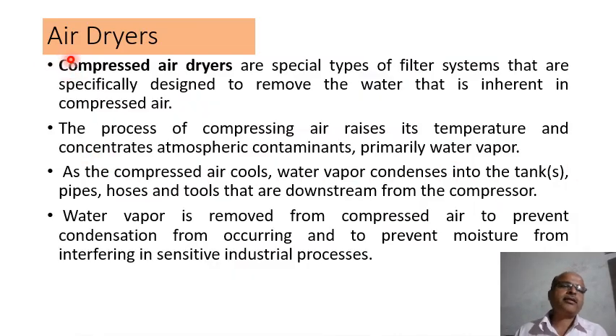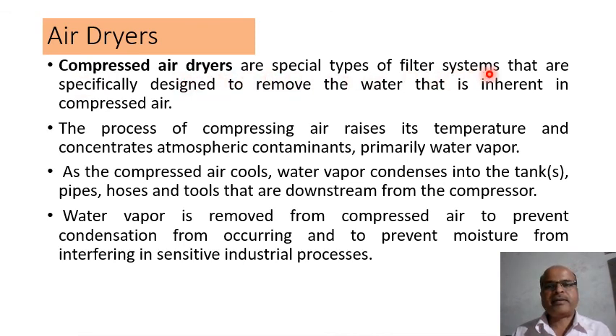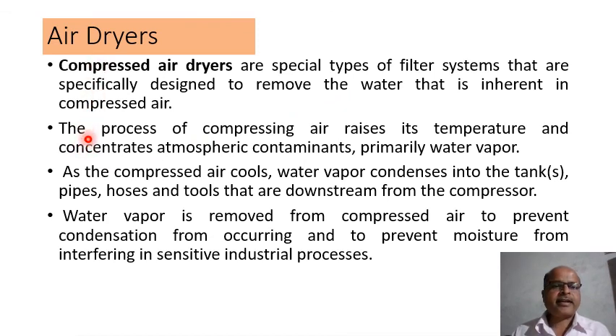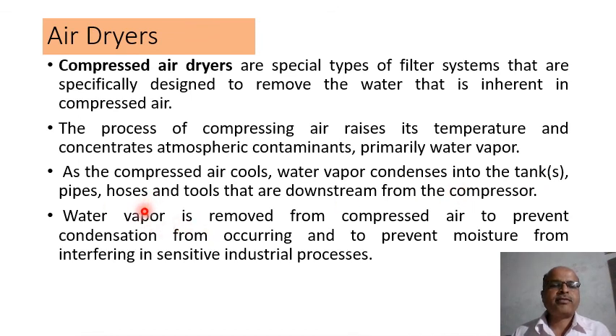The next component in a pneumatic system is air dryers. Compressed air dryers are special types of filter systems specifically designed to remove water that is inherent in compressed air. When air is compressed, water vapors are generated due to the cooling effect and must be dried. The process of compressing air raises its temperature and concentrates atmospheric contaminants, primarily water vapor. As compressed air cools, water vapor condenses into tanks, pipes, hoses, and tools downstream from the compressor. Water vapor is removed to prevent condensation and to prevent moisture from interfering in sensitive industrial processes.